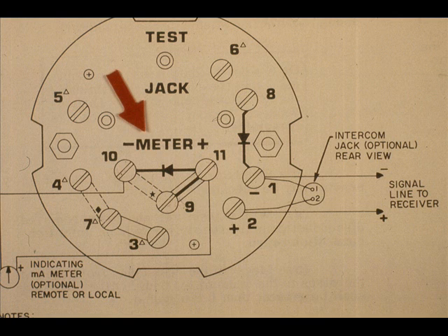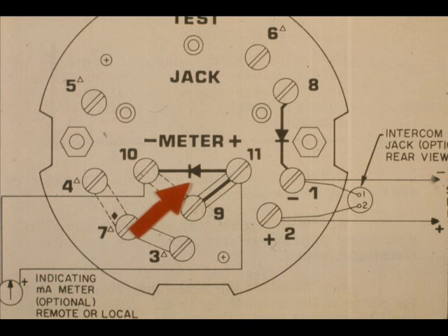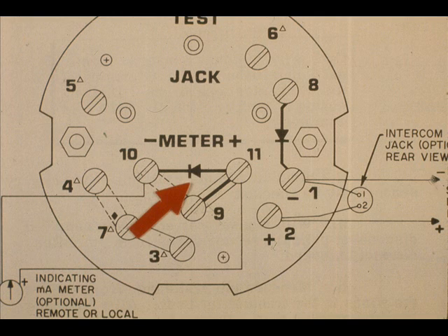The meter, when used, operates below the barrier voltage of the diode and works normally. No current passes through the diode. If the meter opens up, the voltage across 10 and 11 immediately increases and surpasses the diode barrier voltage causing it to conduct. This closes the circuit and the loop is back to normal.